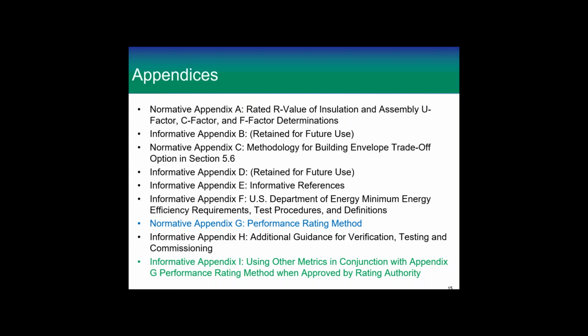Now, informative Appendix F is what we do with the DOE. Officially, ASHRAE has the right to regulate the equipment used in commercial buildings. That's called three-phase equipment, so it's got three-phase power. It's for commercial buildings. ASHRAE's been given the right to regulate that. By regulate, I mean that we're going to set the minimum efficiency requirements for them. Now, the federal government or the DOE sets the requirements for single-phase equipment, residential equipment. They do that. All right.